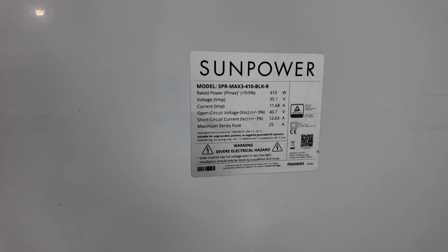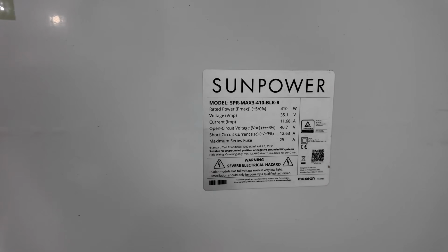Sunpower 410 watt panel, VMP of 35 volts at 11 amps. So at 410 watts, once it converts we should be seeing roughly an absolute maximum of 25 to 30 amps, probably not 30, more so 25 on a fantastic day. But the panel is black, so it will get warm, and the hotter it gets, the less efficient it gets.